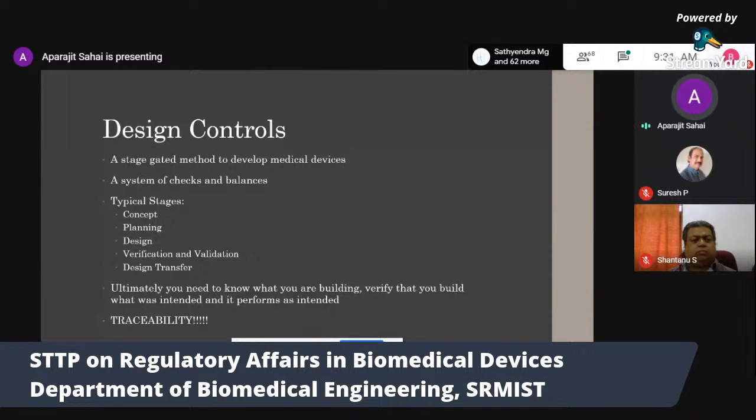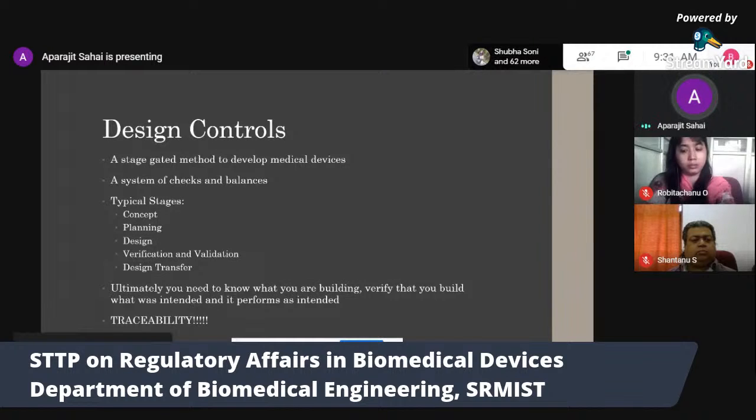Based on what you said, you've intended devices, you want to make a device that is to be used by a patient rather than a physician. Then it essentially has to meet, I think there is a requirement in there that someone with a grade 8 level of education or something like that should be able to use it without undue burden. So that's something you'll have to focus on.